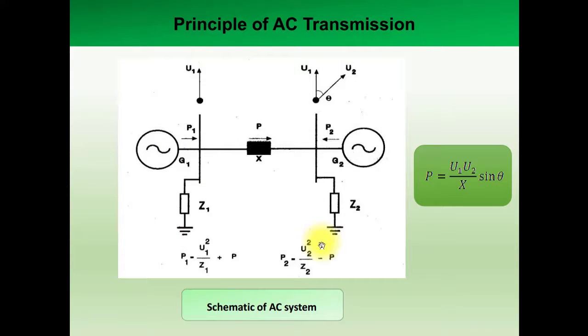Here you can see the voltage at bus 1 is U1 and voltage at bus 2 is U2. So there is a difference of angle between two buses and power is transmitted by creating the angle of difference between two phases in the AC transmission systems.